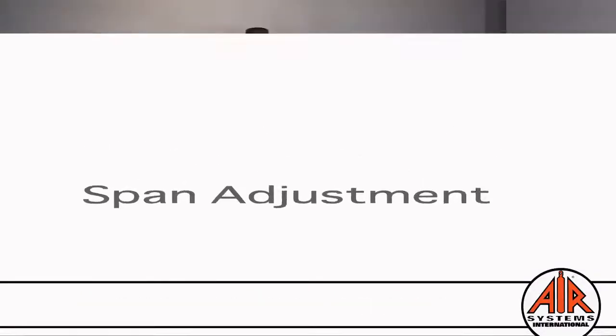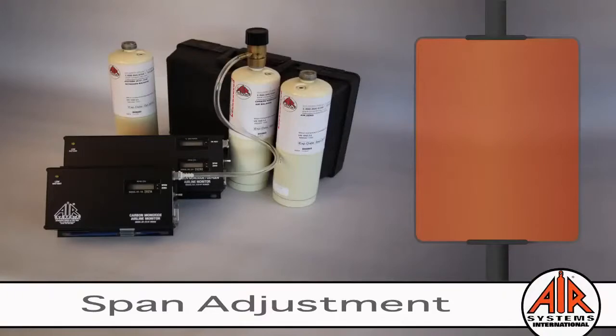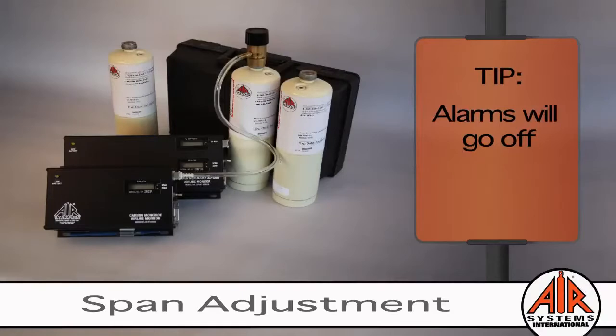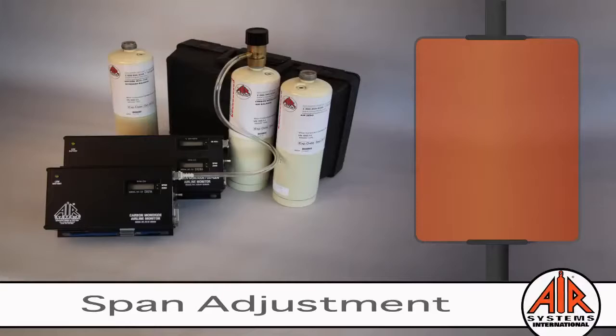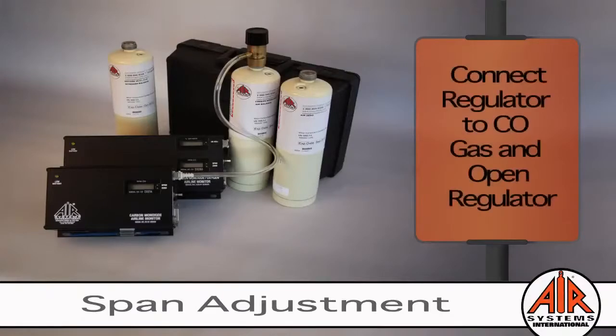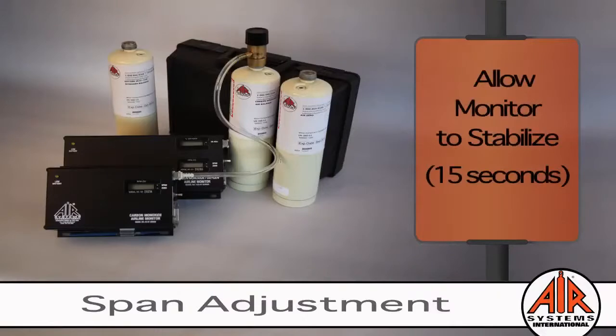Phase 2 of the calibration process is span adjustment. Unless the monitor is removed as shown, it is normal for the alarms to go off during this stage of calibration. The monitor should still be on. To begin the span adjustment, connect the regulator to the carbon monoxide gas cylinder and open the regulator by turning the knob counterclockwise. Allow the monitor to stabilize for 15 seconds or more.